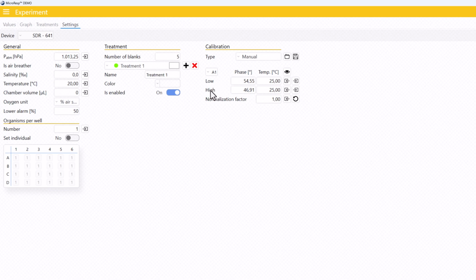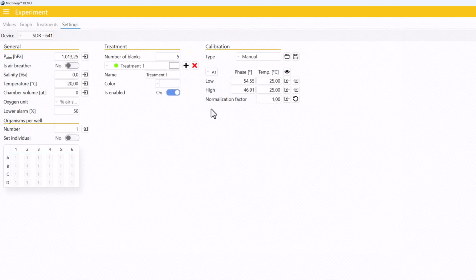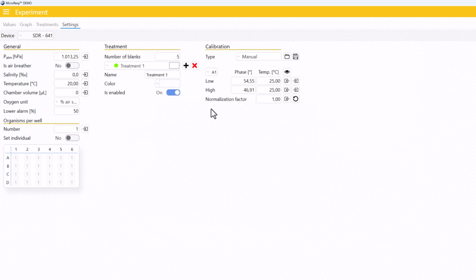The calibration procedure is a little different depending on if you calibrate in water versus in air. If you are calibrating in water, start by keeping the microplate reader, the glass plate, and calibration water within ±1.5 degrees of your experimental temperature for around 60 minutes. This can be done using our optional flow-through water bath or by keeping the entire microplate setup in an incubator or in a temperature-controlled room. Then type in the experimental temperature in the temperature field over here.